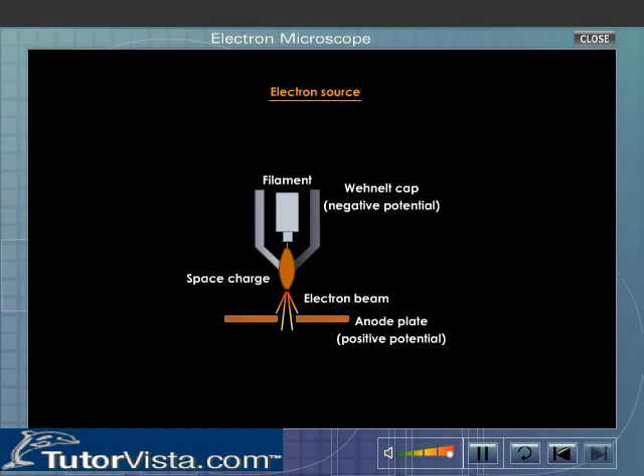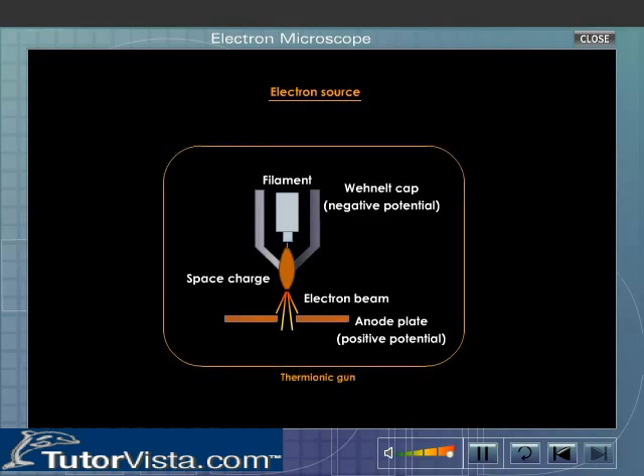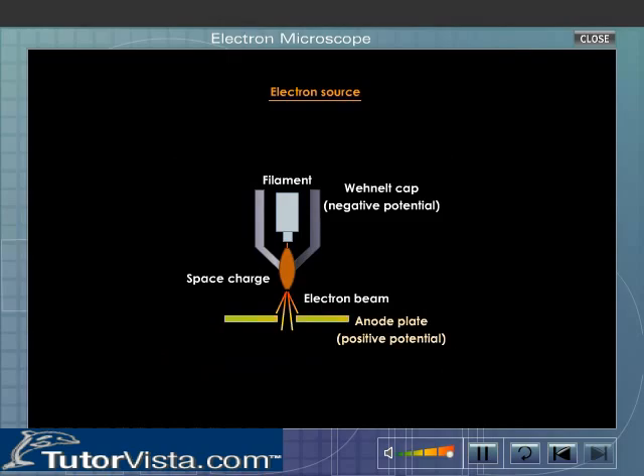Electron Source. All electron microscopes generally use a thermionic gun as a source of electrons. A thermionic gun is shown here. A positive electric potential is applied to the anode plate. The filament which is the cathode is heated until a stream of electrons is produced. The electrons are then accelerated by the positive potential down the column.